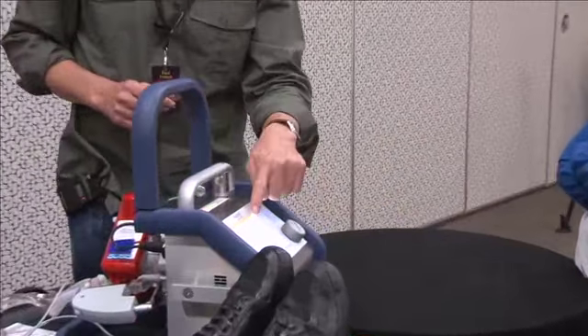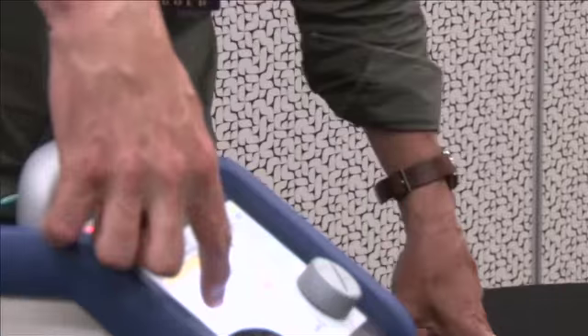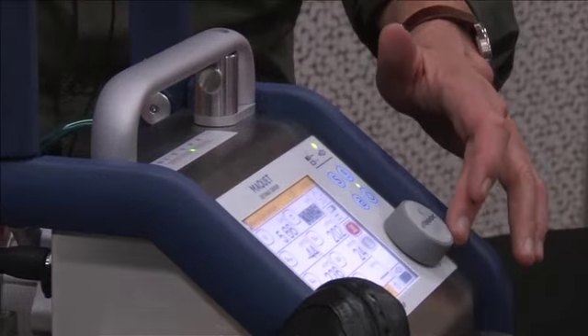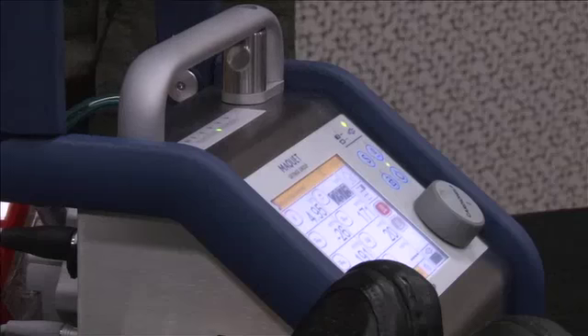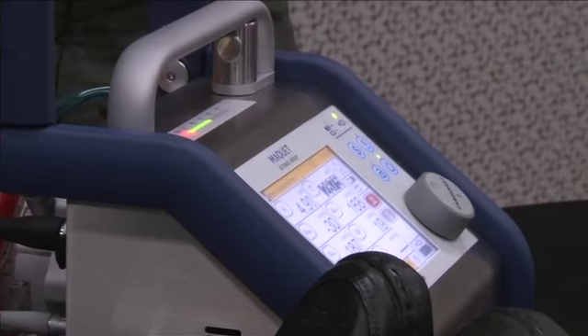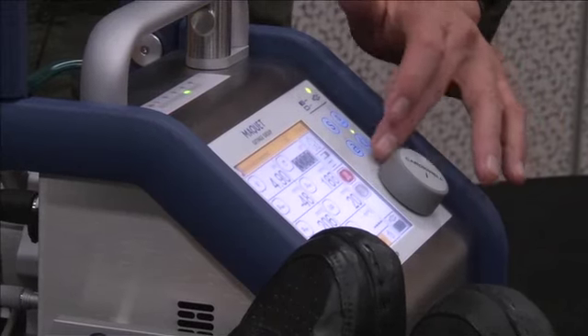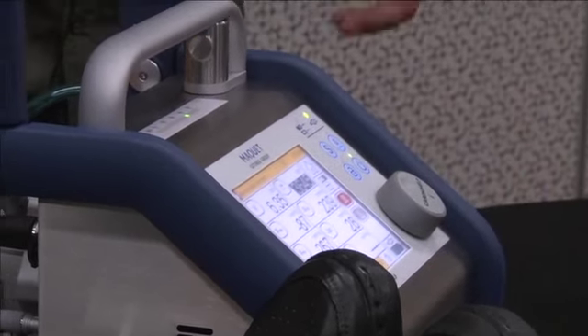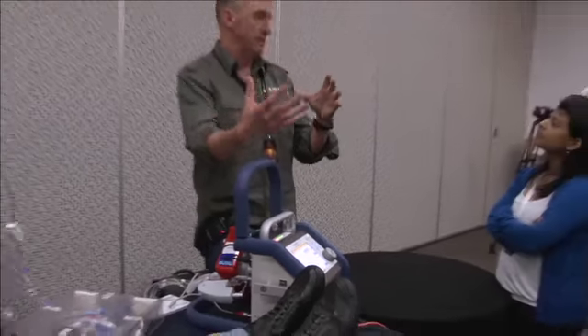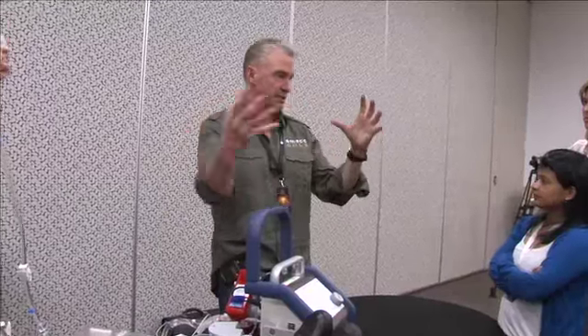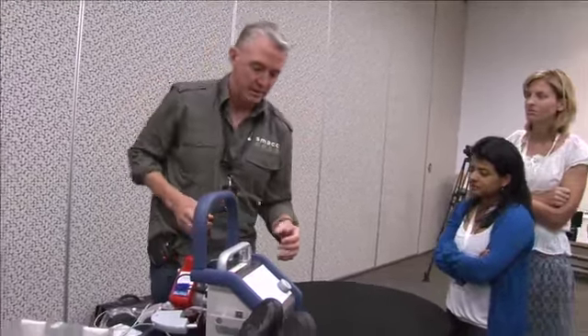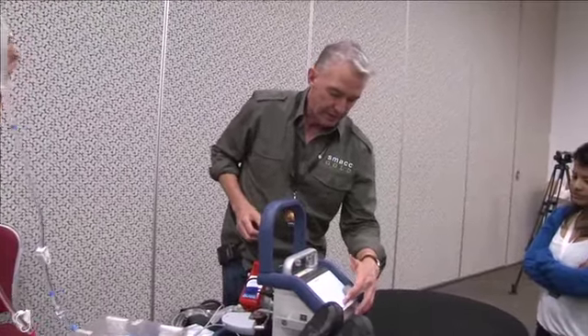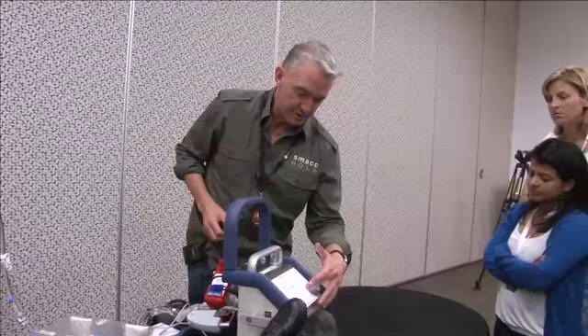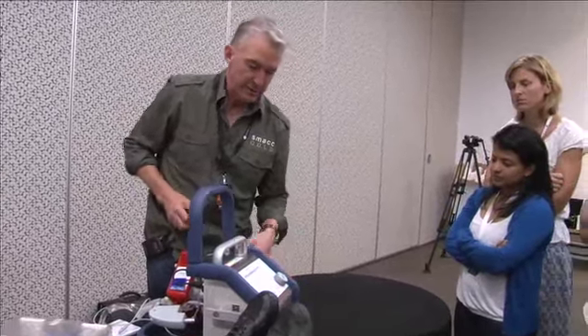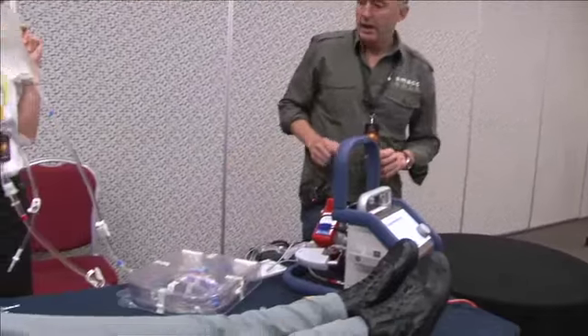And what you can see here is you've got your flow rate being demonstrated. You've got your venous pressure being demonstrated over here. And as we vary the flow rate, what you'll notice is the venous pressure changes. Because this is a non-collapsible tubing, we can run this very hard without any problems, but we're just generating more pressure in the venous line as we do so. Now you can imagine that if you have a vena cava that's exposed to those sorts of pressures, it just collapses down. We've got some bubble sensors which can now reset because we've reprimed the circuit, and smooth sailing.